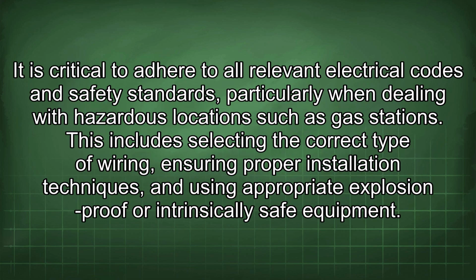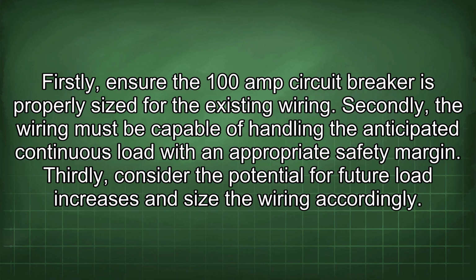It is critical to adhere to all relevant electrical codes and safety standards, particularly when dealing with hazardous locations such as gas stations. This includes selecting the correct type of wiring, ensuring proper installation techniques, and using appropriate explosion-proof or intrinsically safe equipment. Firstly, ensure the 100 amp circuit breaker is properly sized for the existing wiring.